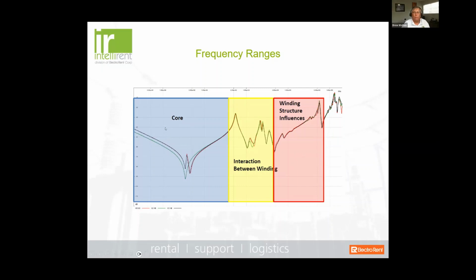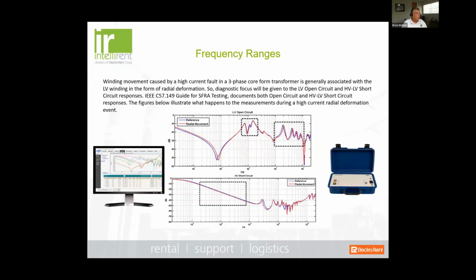Now, in terms of your response that you're getting from your SFRA test, we can kind of identify what portion of the transformer we may have an indicated problem. The lower frequencies indicate problems within the core itself. And then in the middle frequencies, this is an interaction between the core windings. And then in the higher frequencies, this would indicate an issue in the winding structure itself. So this kind of pinpoints exactly where in the transformer we may have a problem.